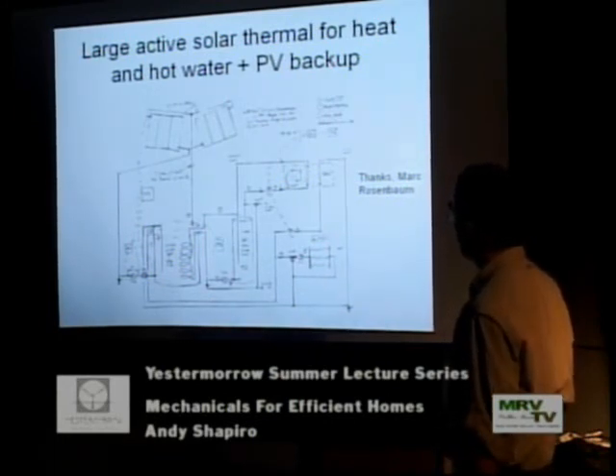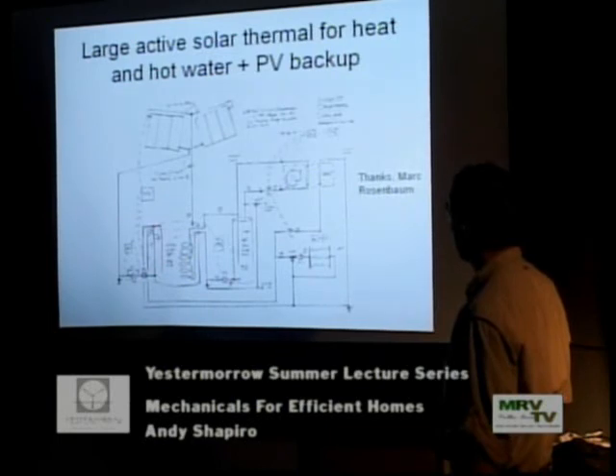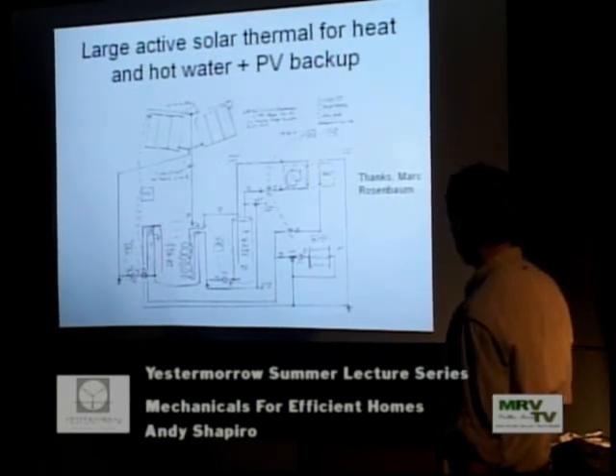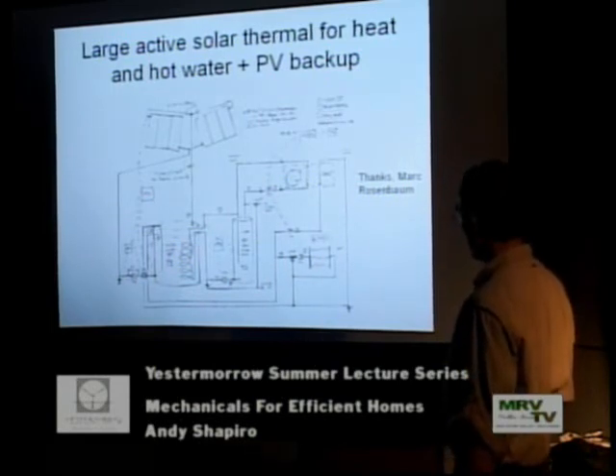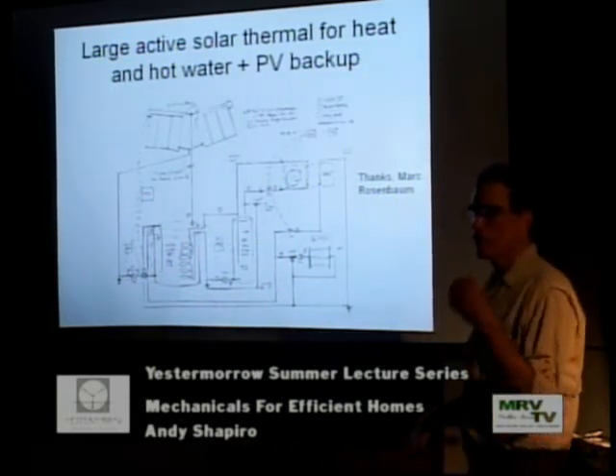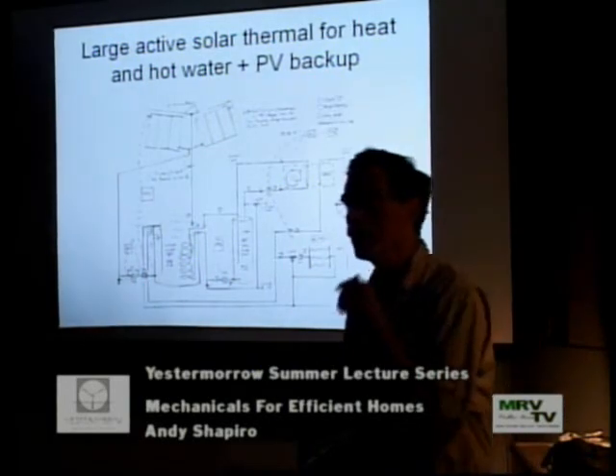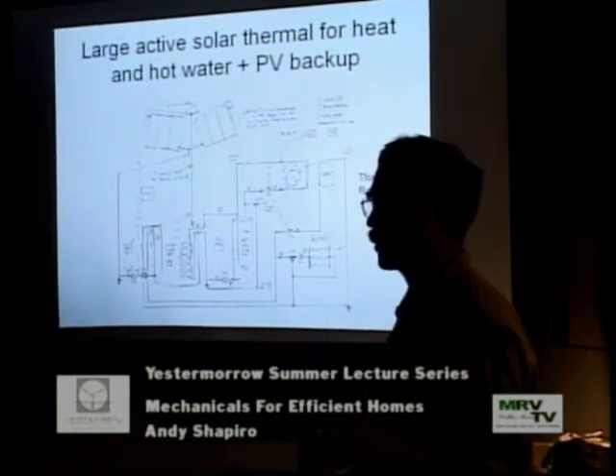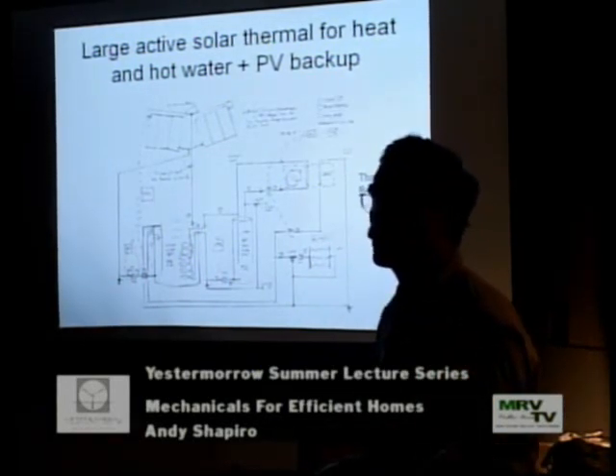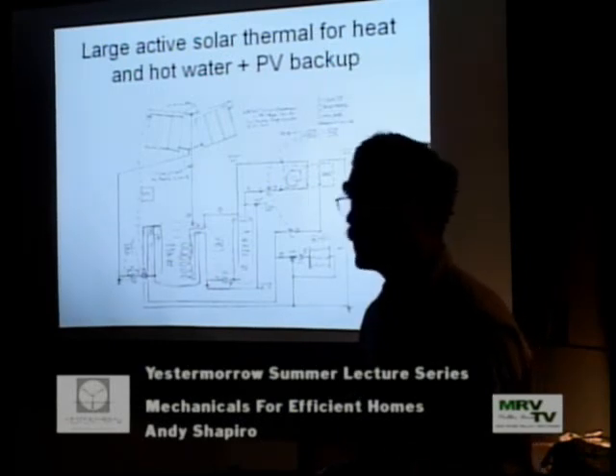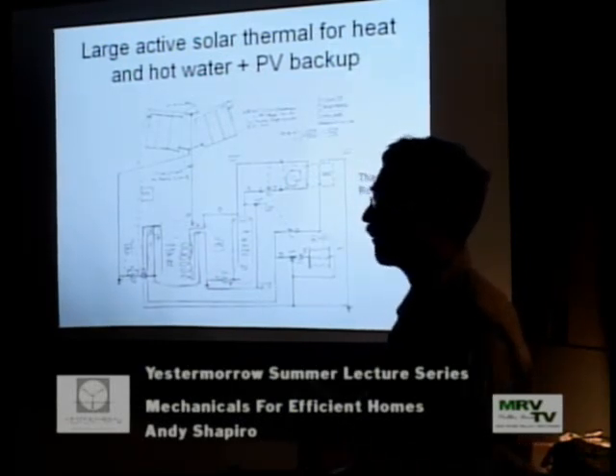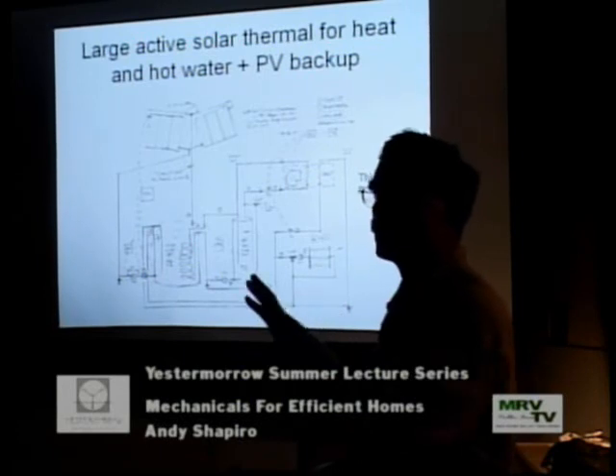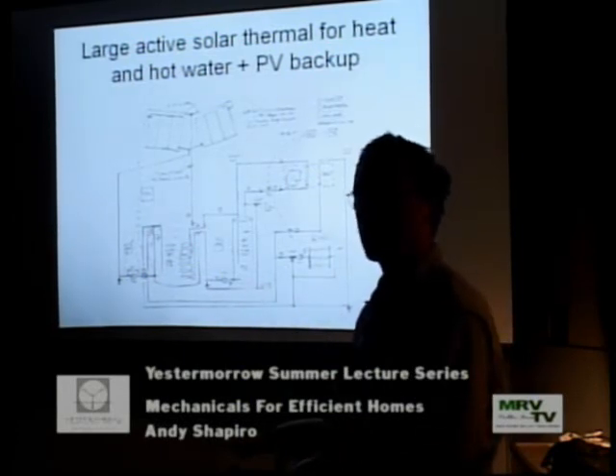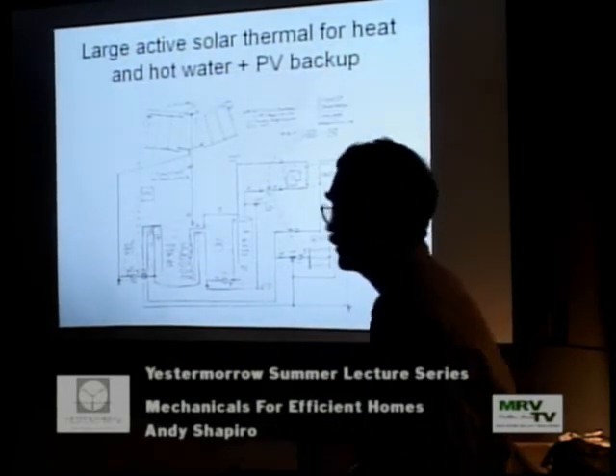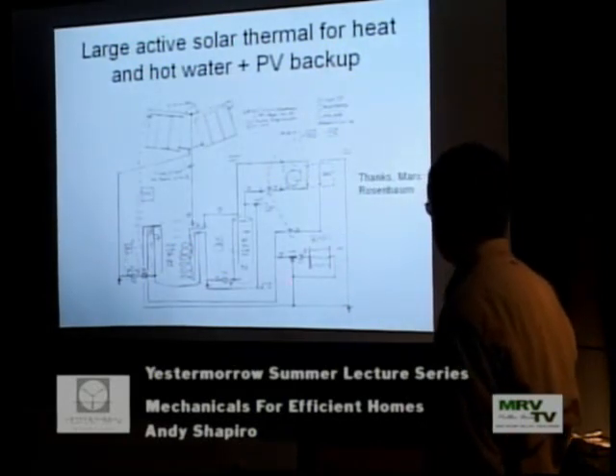The radiant tubing runs right off the tank, the solar tank water, so we can run that water through the tubing to heat the floor. Because this is radiant floor heating with concrete, it's a good match for solar thermal, since you only need about 100-degree water, and you can even get heat out of 80 or 90-degree water. Solar thermal systems need the distribution to be very low temperature to get the best use out of the solar energy, so radiant is a good match.